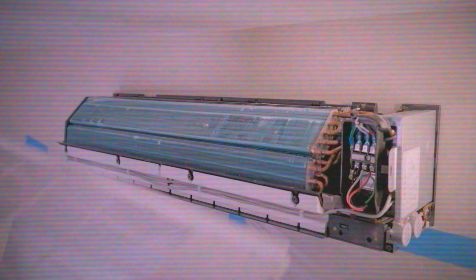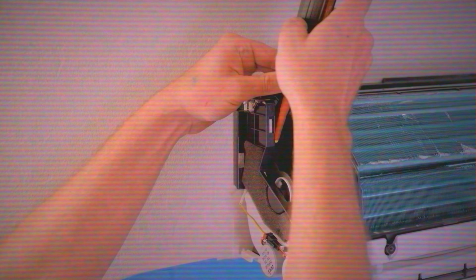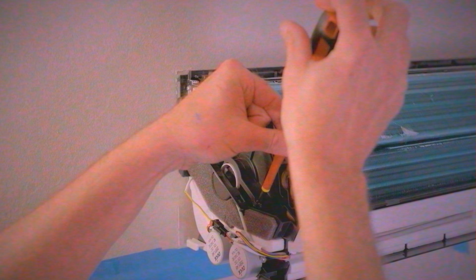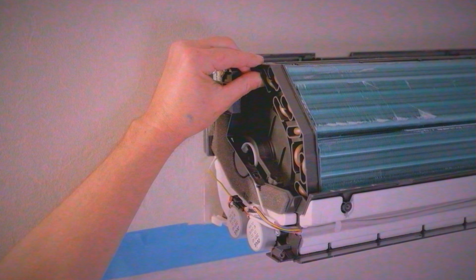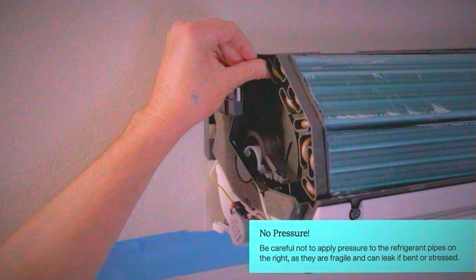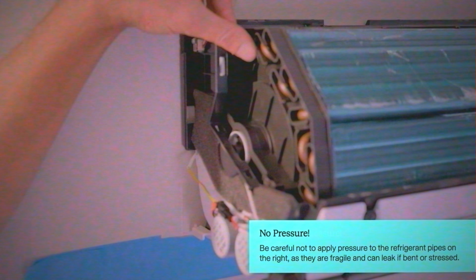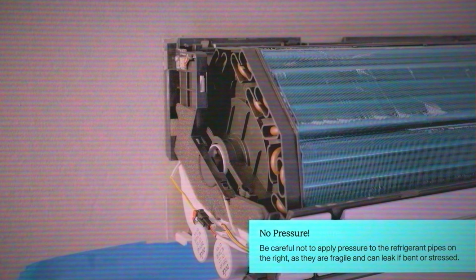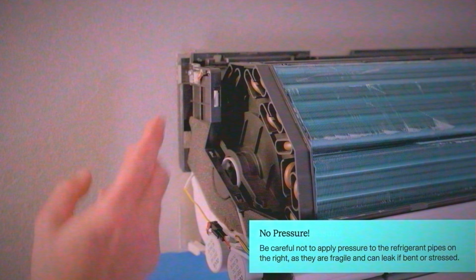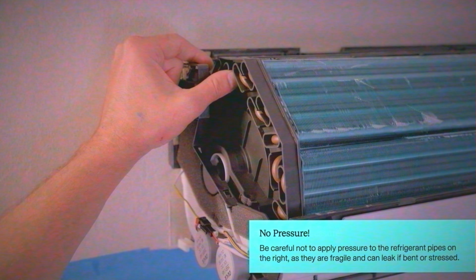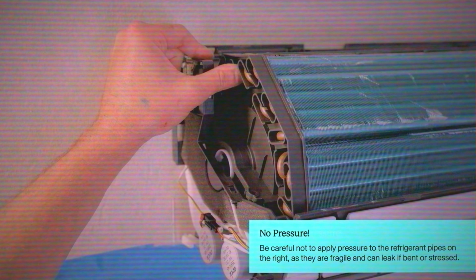Finally, let's unscrew the heat exchanger. There are 4 screws holding the heat exchanger, 2 on the left and 2 on the right. If the heat exchanger needs to be lifted to clean out debris, only lift from the left side, and no more than 2 inches, or about a 28-degree angle. Be especially careful not to apply pressure to the refrigerant pipes on the right. These are fragile and can leak if bent or stressed.